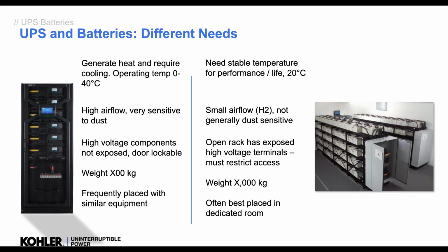Now the battery needs to have a stable temperature for best performance and for lifespan. There's a small amount of hydrogen coming out of it. It's not so dust sensitive, but we should still keep it in a good environment. If we've got a big room like we're looking at here, we want to control that room. The battery voltages are dangerous, so it's often best in a dedicated room, or we partition the room off for those batteries. So we just have to consider the weight, the safety and the temperature, a lot more considerations around the battery than a lot of people do.